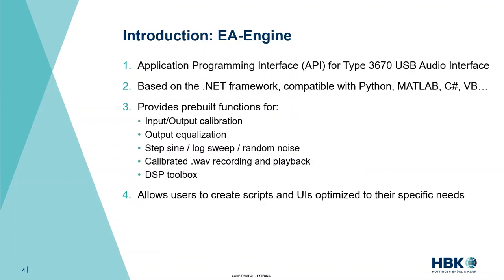The EA Engine is an application programming interface, or API, that accompanies the 3670. It uses the .NET framework, meaning it is compatible with a host of languages that support .NET. Today I'm covering Python, but it also works with MATLAB, Visual Basic, and lots of others. Any language with a .NET package will be able to work with the EA Engine.